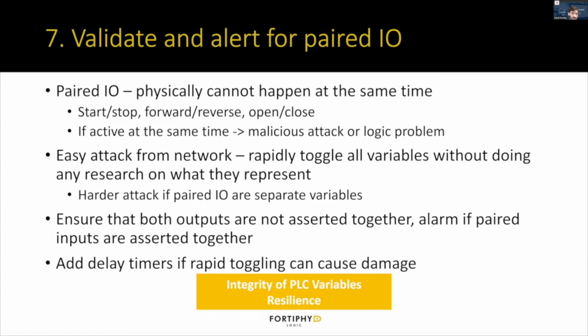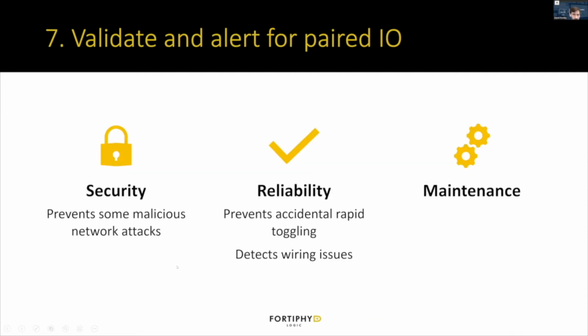Another variation on this, something else you can add, is delay timers on I/O if rapid toggling can cause damage. A motor starting and stopping very rapidly can maybe wear out the motor faster, so maybe you want to add a delay timer to make sure it does not get toggled too rapidly to cause any problems. For security, this helps prevent some malicious network attacks. For reliability, it helps prevent just accidental rapid toggling.